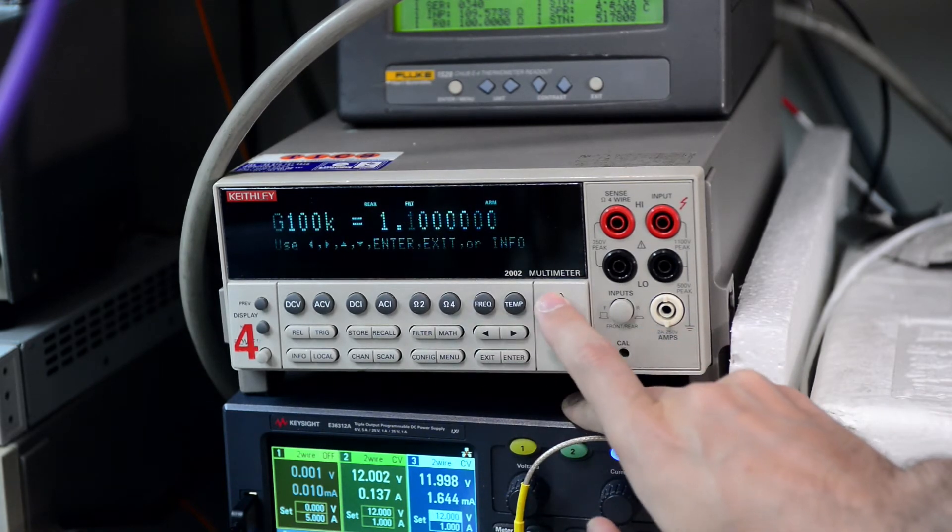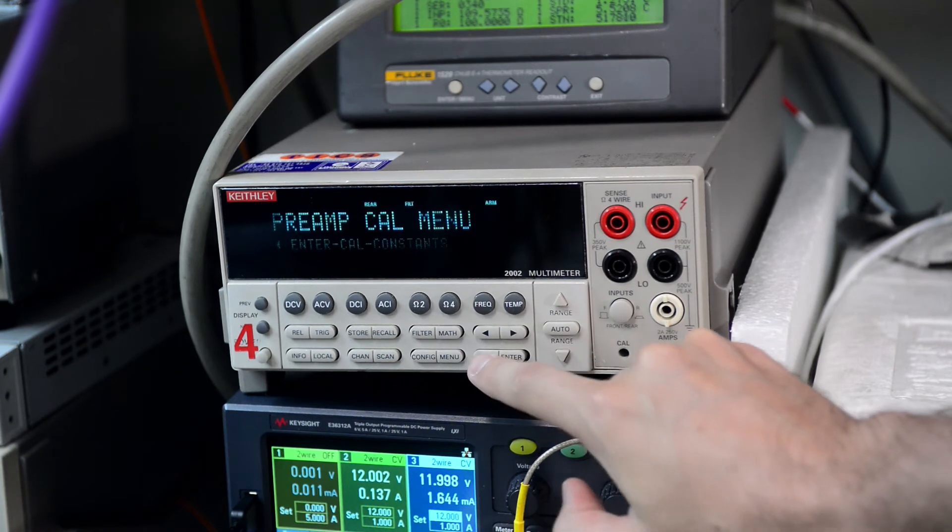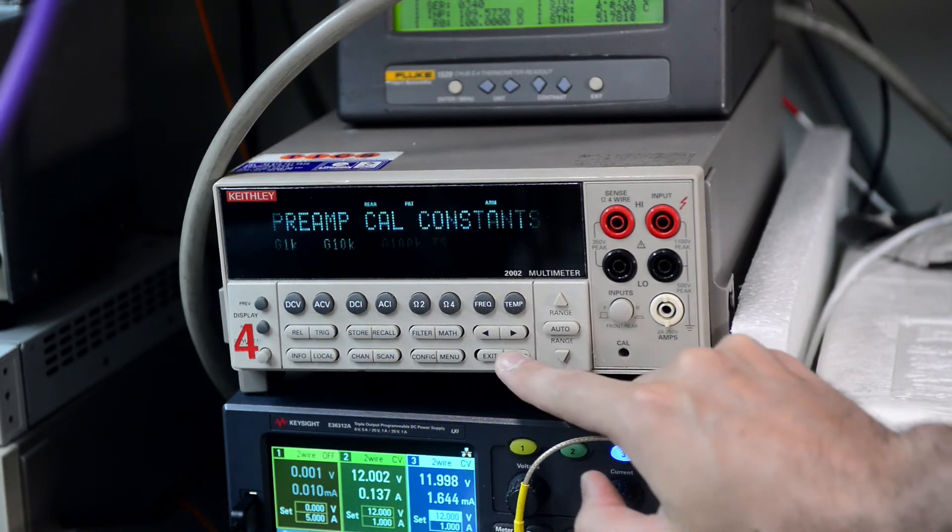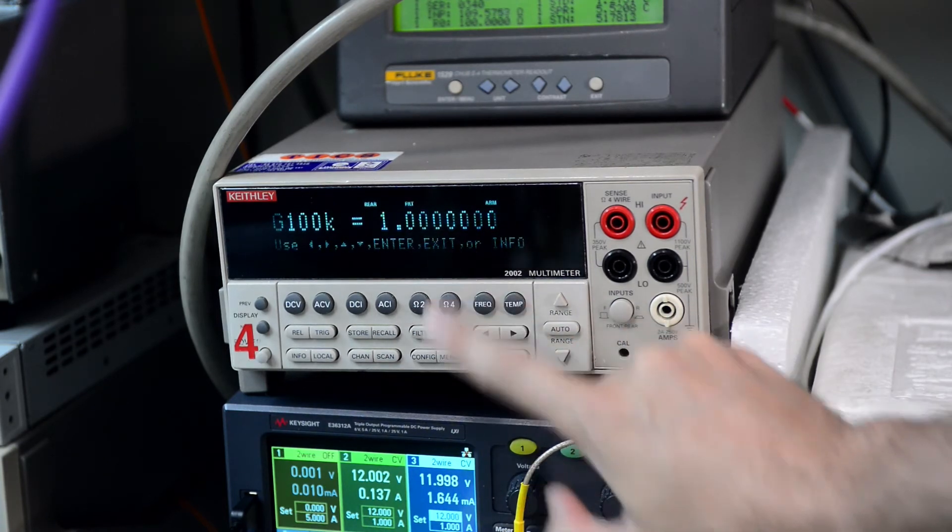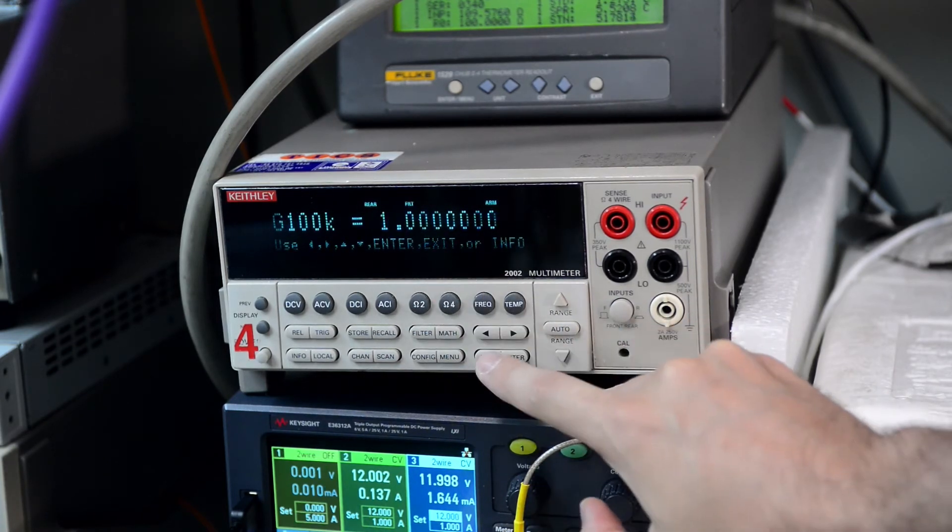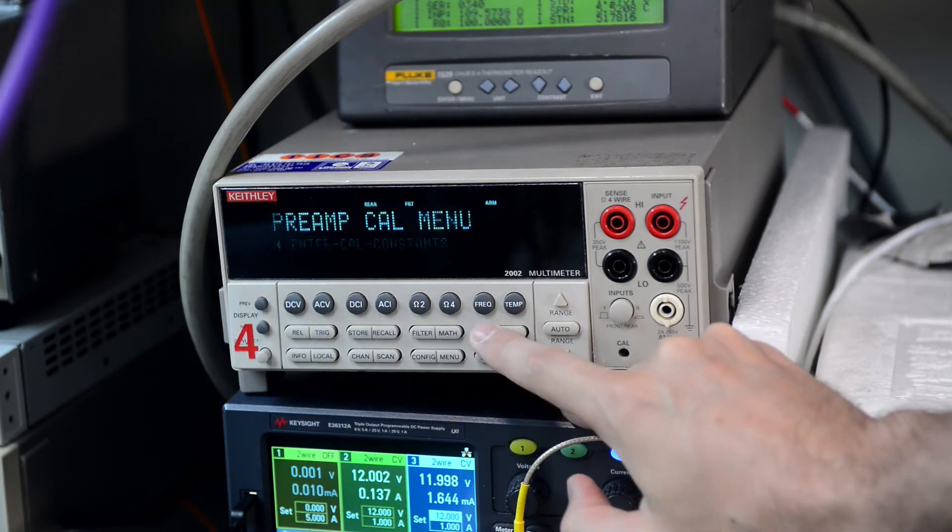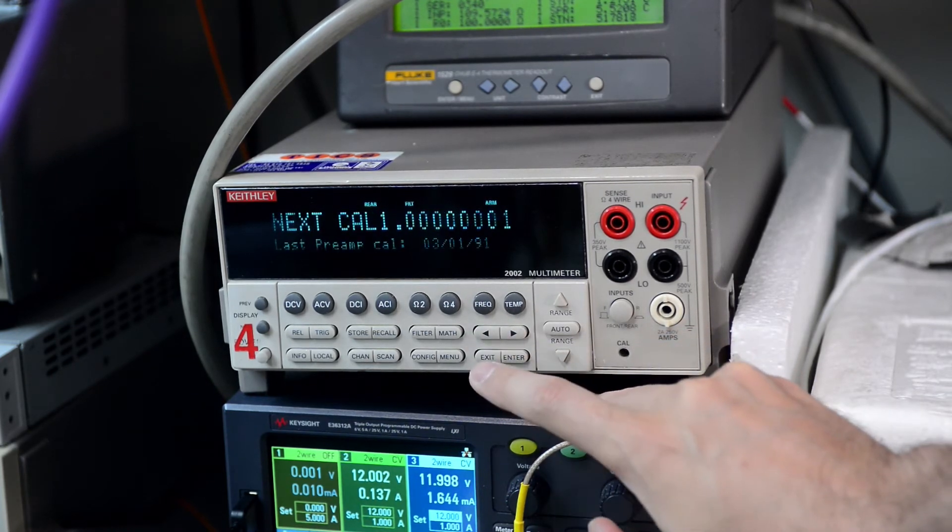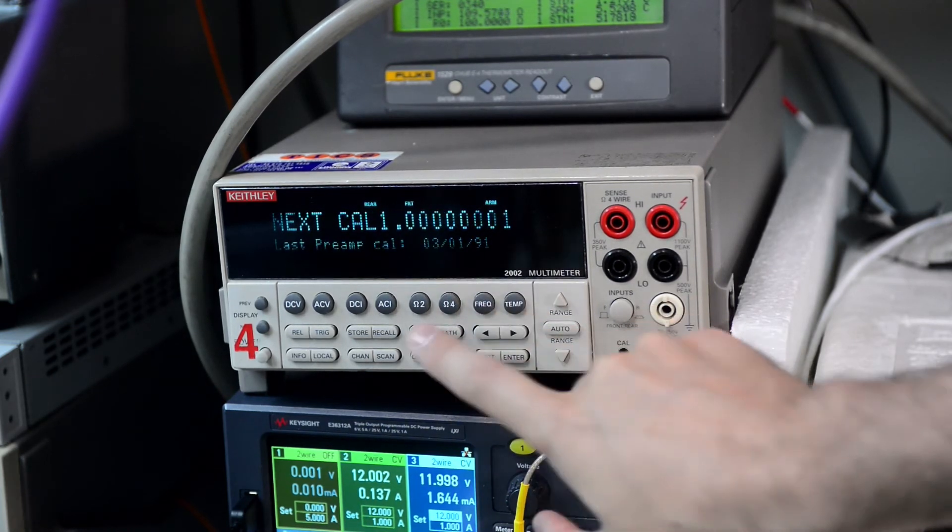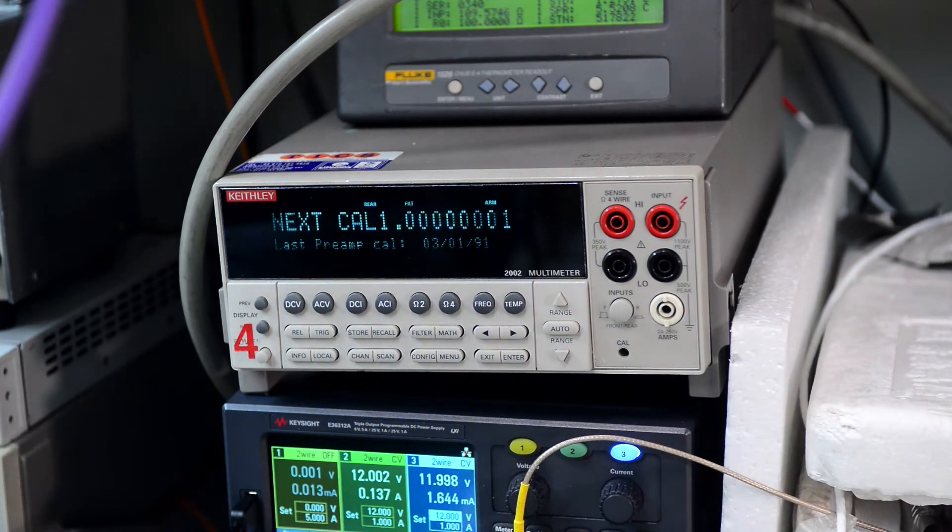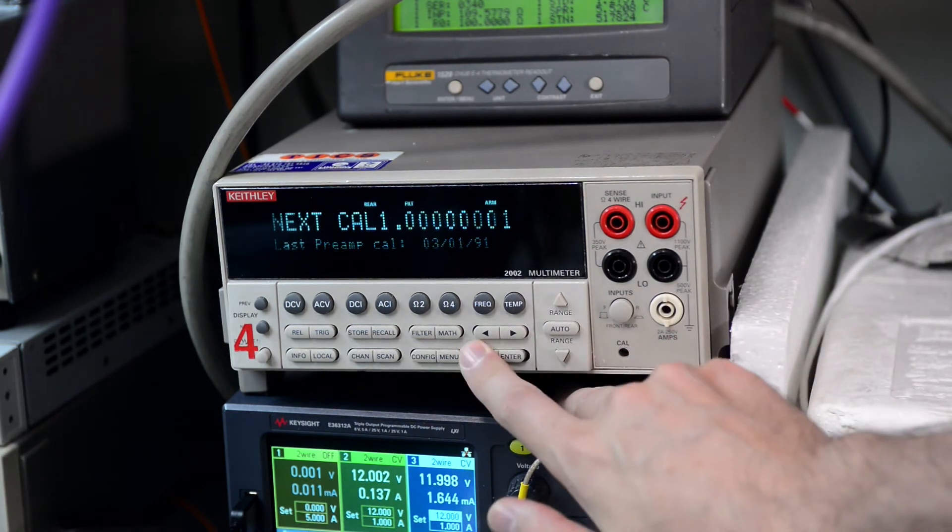And now 100k, change, but it doesn't read back correctly. It just reads always default 100. And if we try now to check the calibration date, it's corrupted, showing 100 instead of the date.